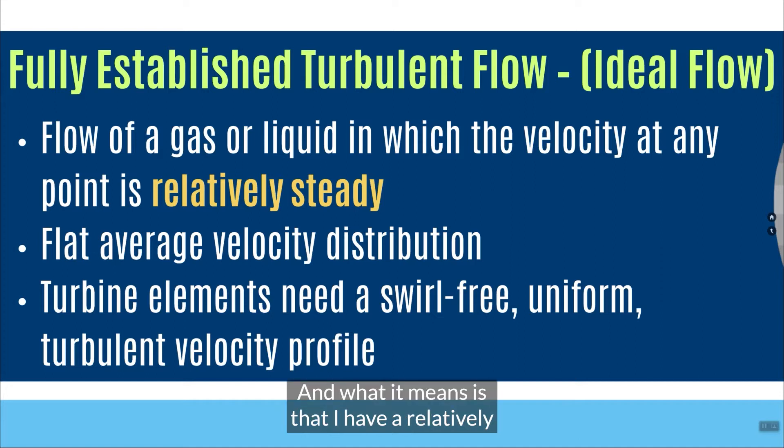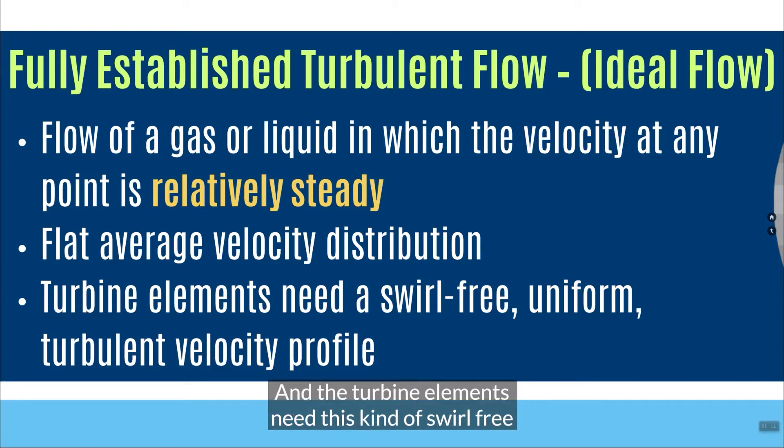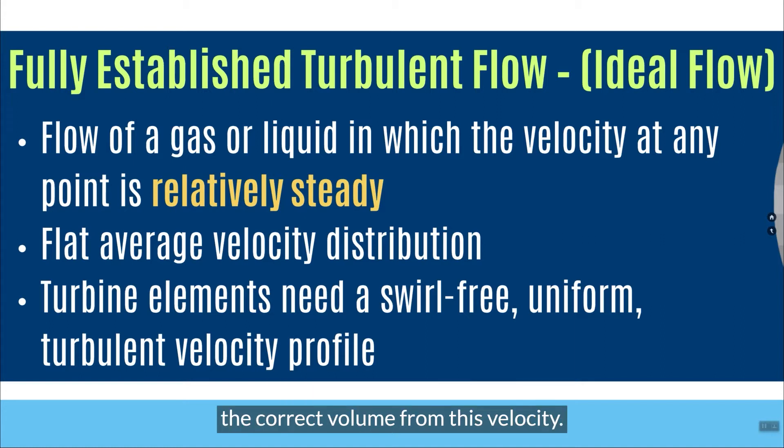And what it means is that I have a relatively steady velocity across the pipe section. And I'm going to show you a picture of that in a second. The average velocity is somewhat flat. It's not skewed. And the turbine elements need this kind of swirl-free, uniform, turbulent velocity profile in order to infer the correct volume from this velocity.